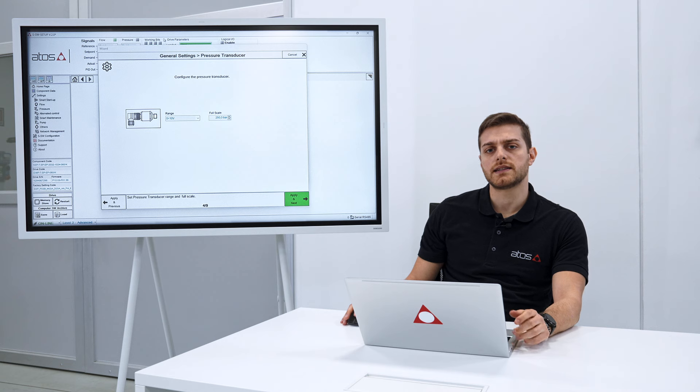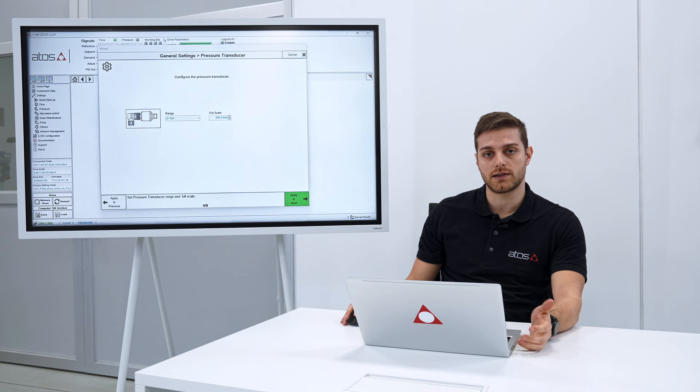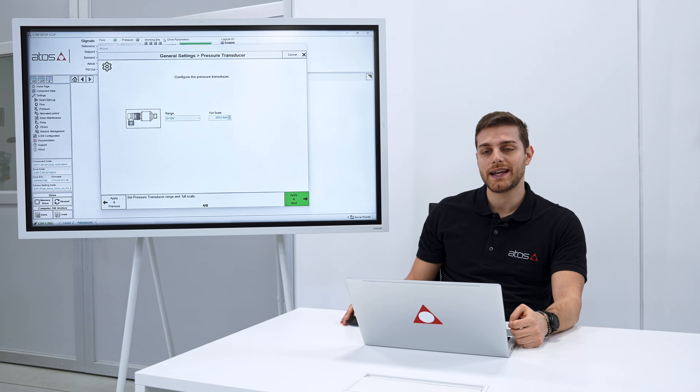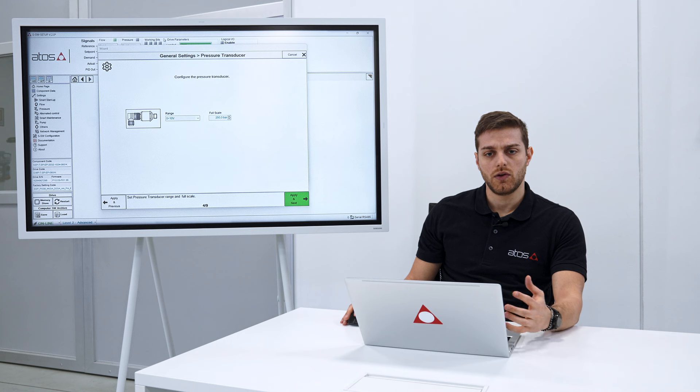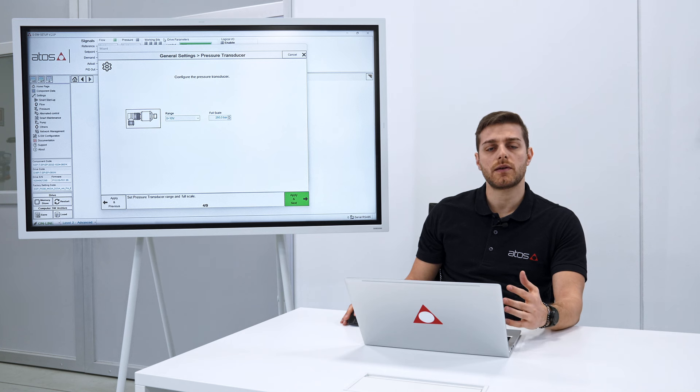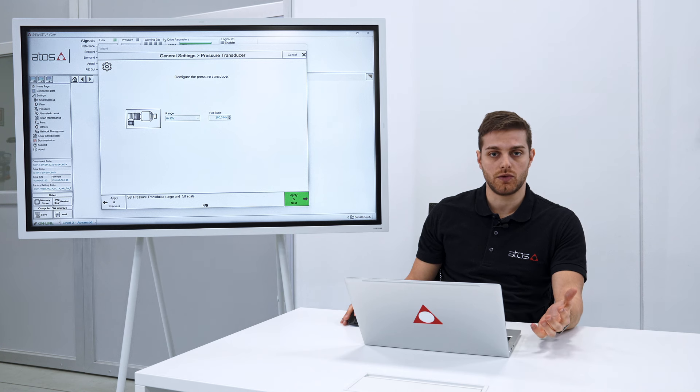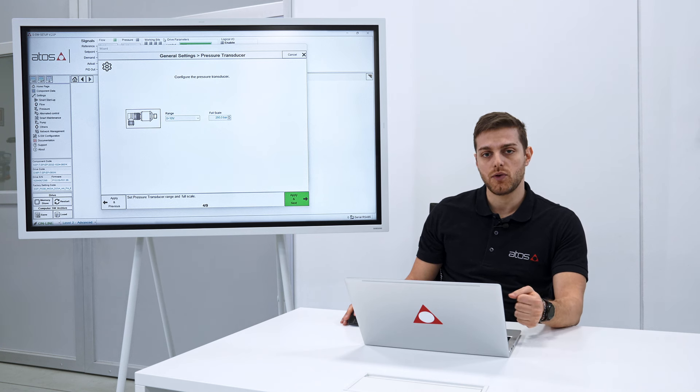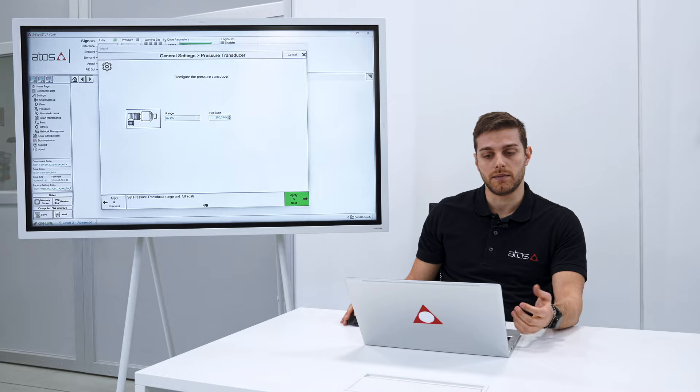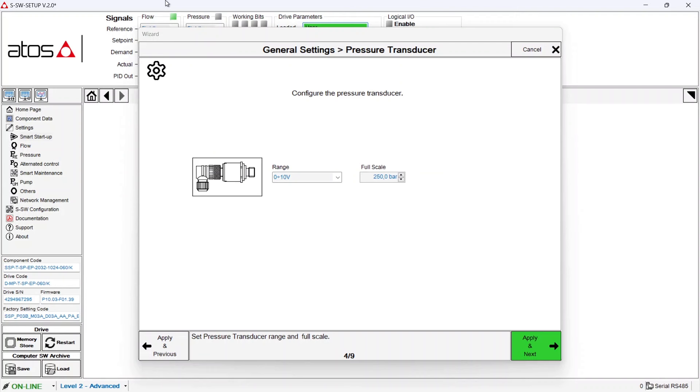The servo pump also needs a pressure transducer to be directly connected to the drive. You can use whatever pressure transducer you want but here in this step you need to set it. In this case let's pretend to use a 0 to 10 volt transducer with a full scale of 250 bar.